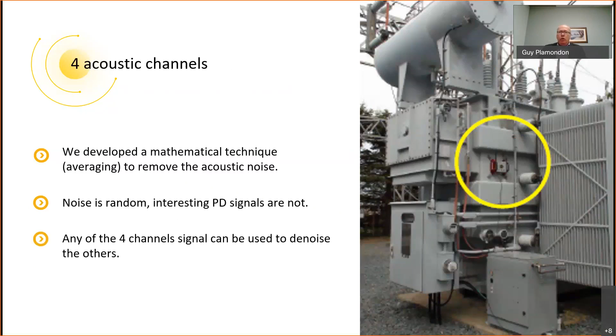Now the averaging technique. This is an example of acoustic acquisition. So it's an original waveform in which the PD is hidden. So here we have acquisition of 2 acoustic channels. And what the software does is set a threshold between the noise level and the original waveform peak amplitude. And we take multiple samples and we divide them by each other. So this way we can eliminate what is random and we keep the acoustic signals that are synchronized.